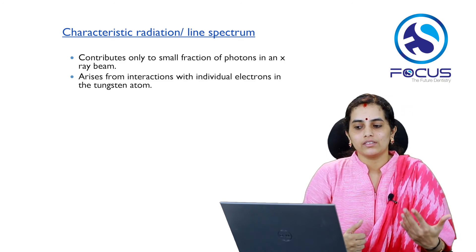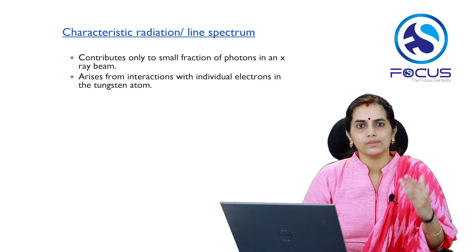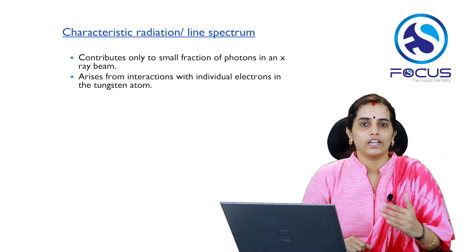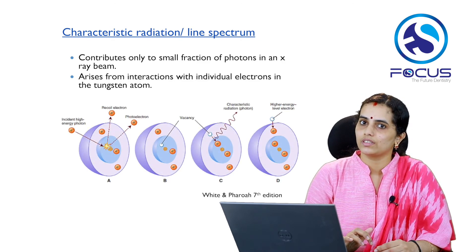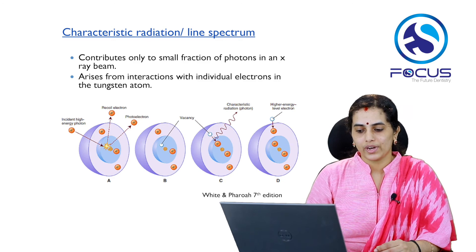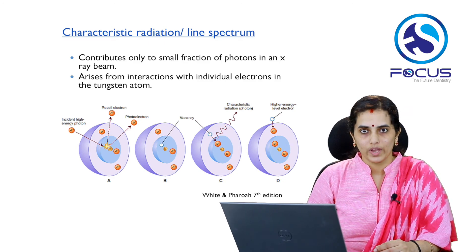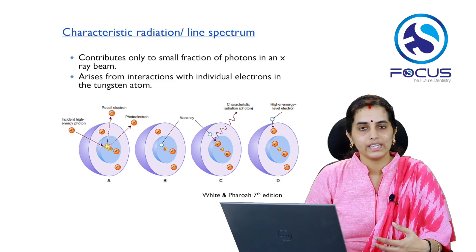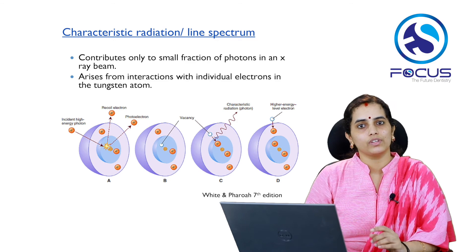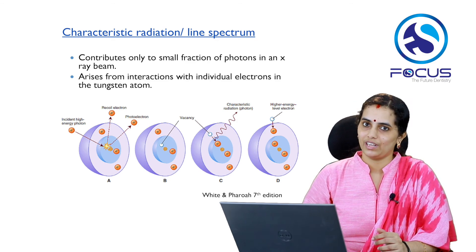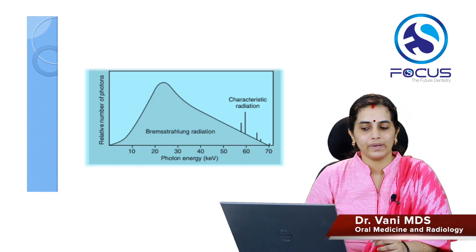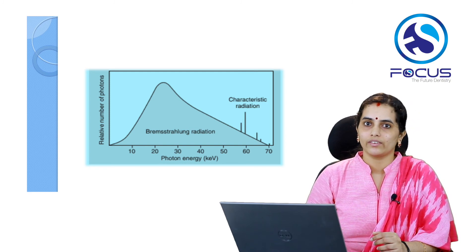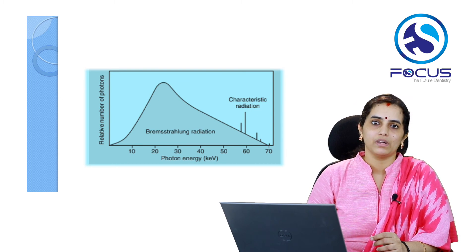Characteristic radiation, or the line spectrum, contributes only a small fraction of photons in an X-ray beam. It arises from the interaction of electrons with individual inner orbital electrons of the tungsten atom. The incident high-energy electron strikes an inner orbital electron and ejects it, creating a vacancy. Electrons from higher energy levels then fill the vacancy, releasing energy corresponding to the difference in energy levels of the orbitals. The graph shows that Bremsstrahlung radiation produces the maximum number of photons, while characteristic radiation contributes only minimally.